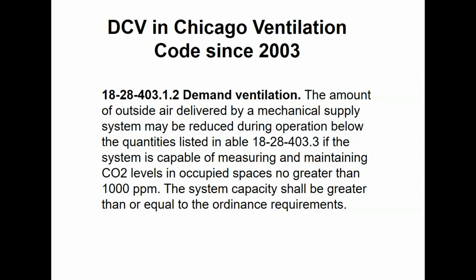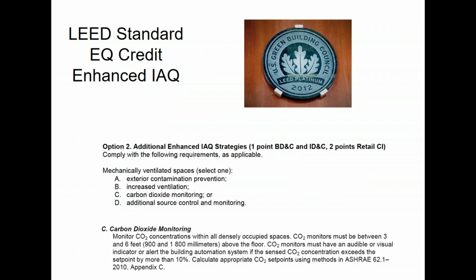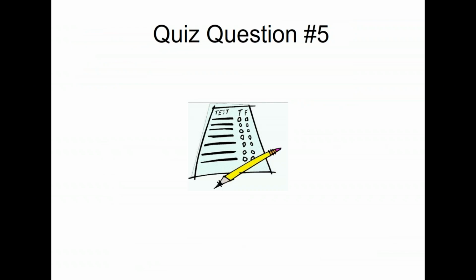Paul asked the question, did I say Wisconsin was 7.5 CFM per person or square foot? It's 7.5 CFM per person in the state of Wisconsin for ventilation code for an office building, or almost all spaces for that matter. There's very few exceptions to that. If you guys are doing LEED projects, CO2 does tie into that discussion as well. For densely occupied spaces, if you want to get a specific credit, you have to do outside air airflow monitoring on the main, and then CO2 monitoring in the spaces that are densely occupied. So there's another tie in there. I know LEED's not really a code, it's more of a standard, but we kind of threw it in there.